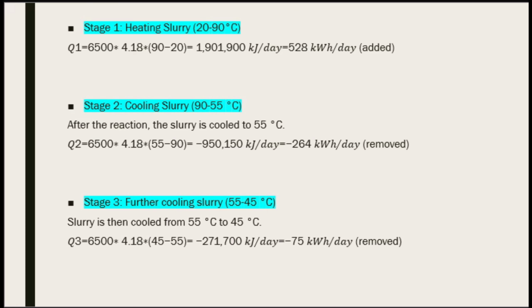In stage 3, the slurry cools further from 55 degrees to 45 degrees, removing 271,700 kilojoules per day, or 75 kilowatt hours per day. Together, the two cooling stages release around 339 kilowatt hours per day of recoverable heat energy that could be reused later in the process.